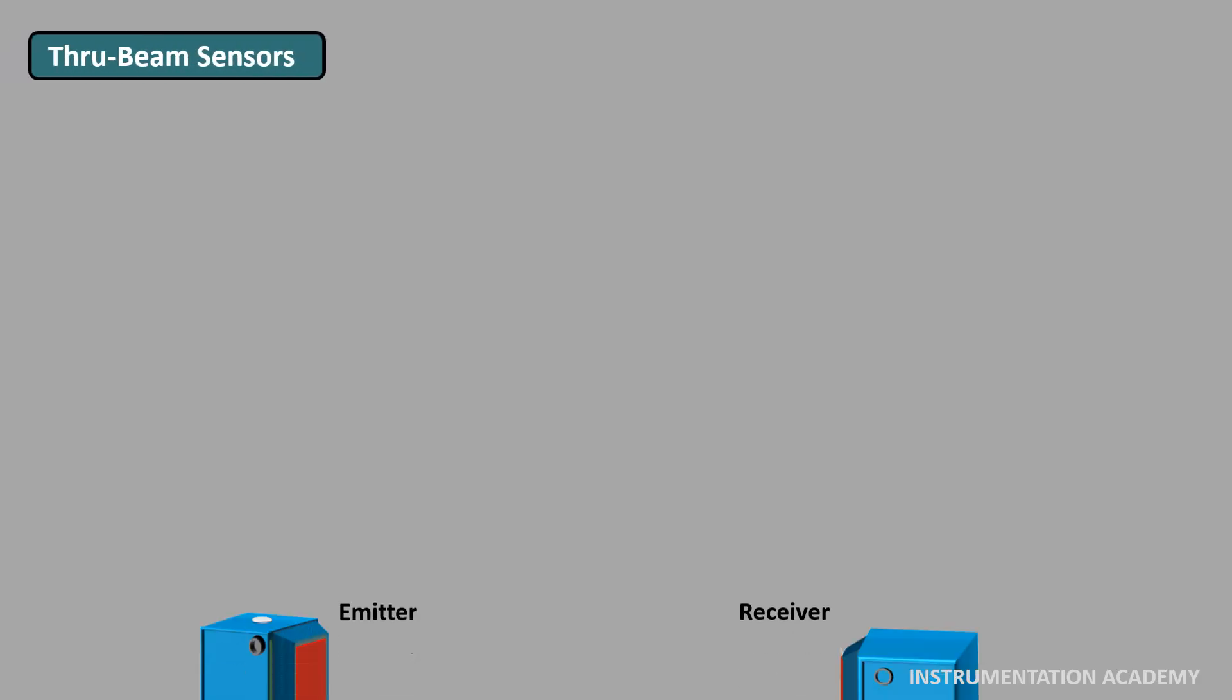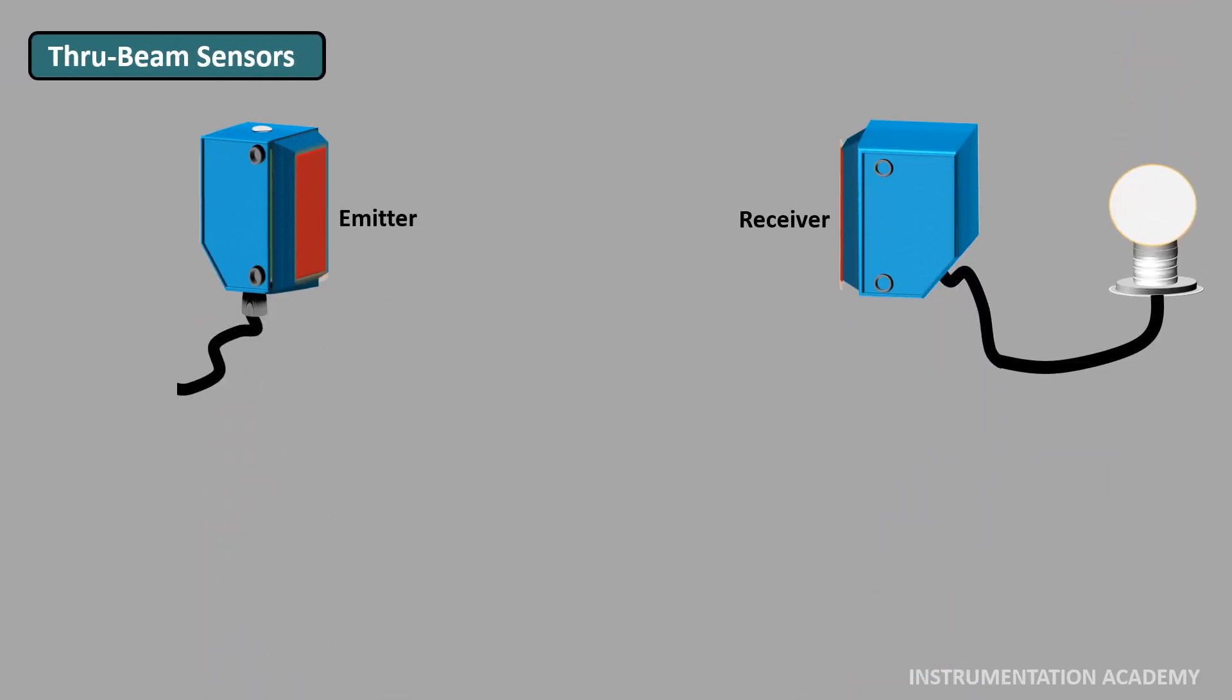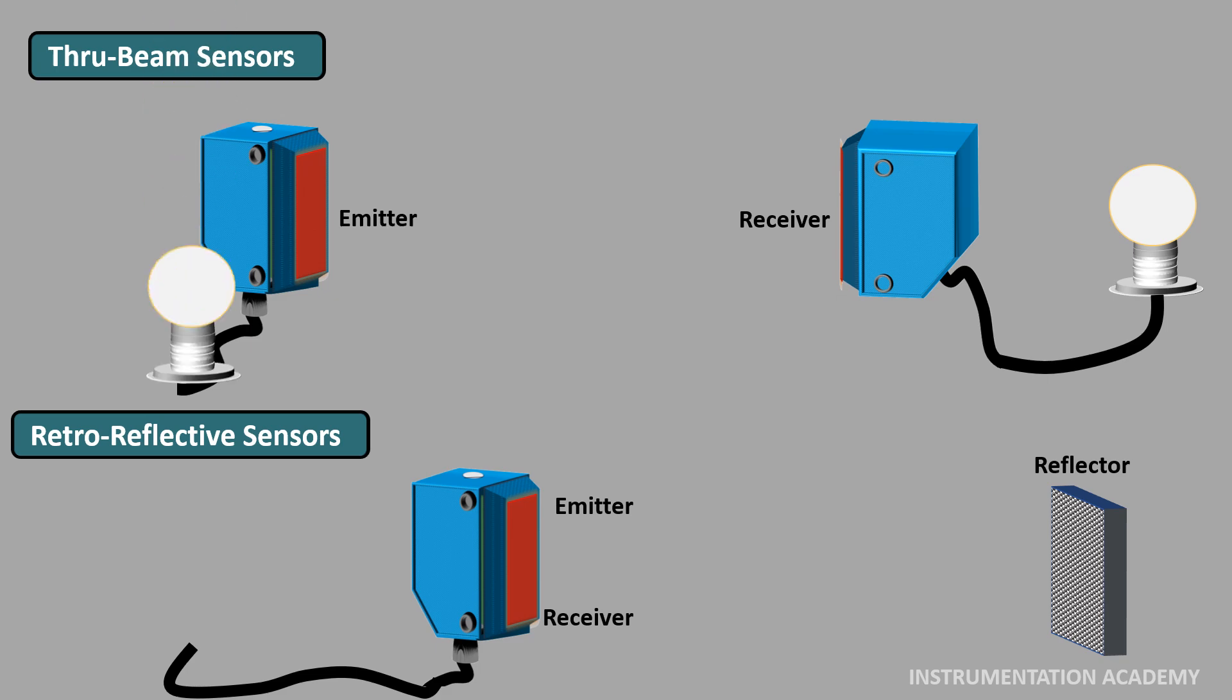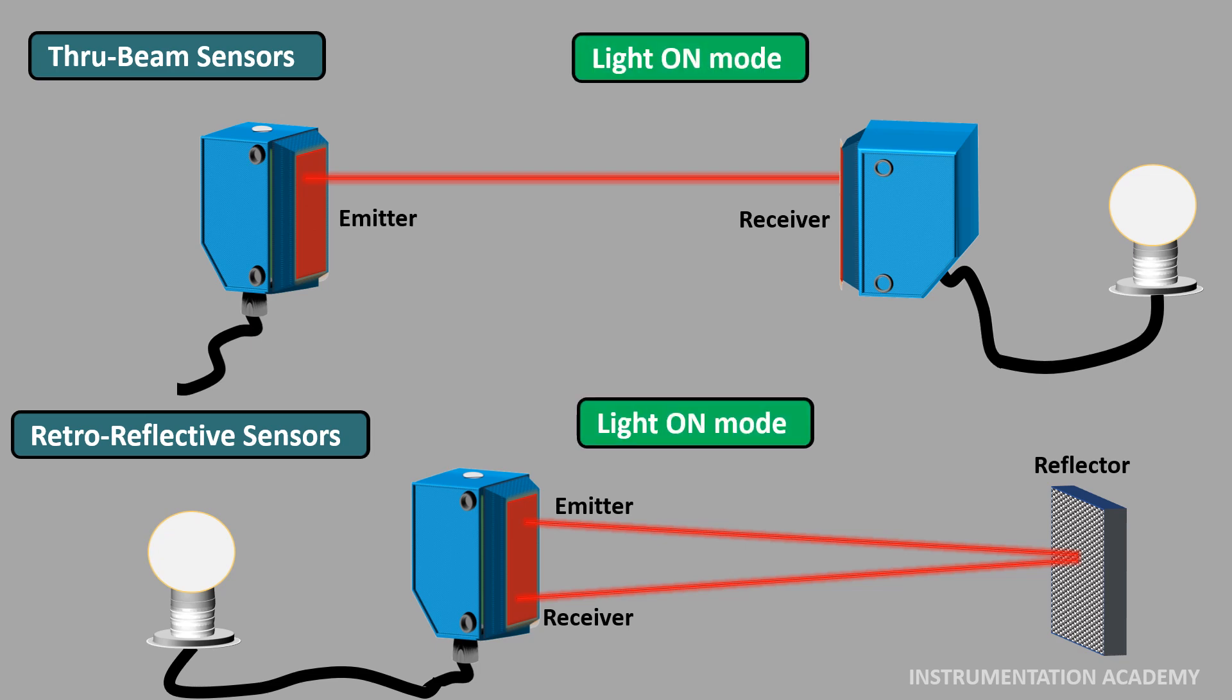Consider that a through beam sensor is connected to a bulb and a retro reflective sensor is connected to another bulb. In both these cases, the receiver receives light normally from the emitter even before the object interrupts the beam of light. In light on mode, as the output is energized when the receiver receives light from the emitter, the bulb glows. While in dark on mode, as the output is not energized when the receiver receives light from the emitter, the bulb will be switched off.